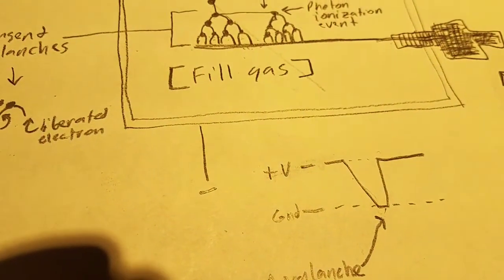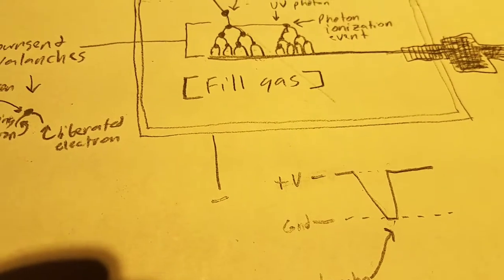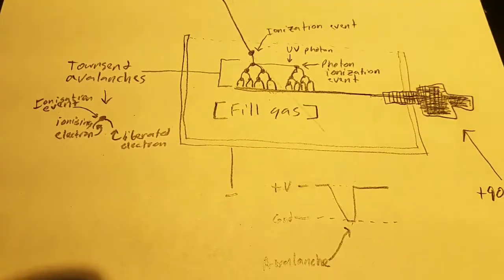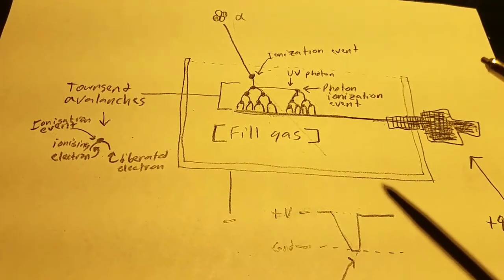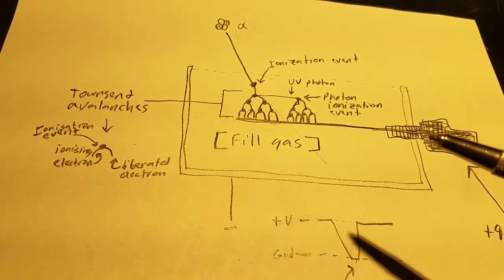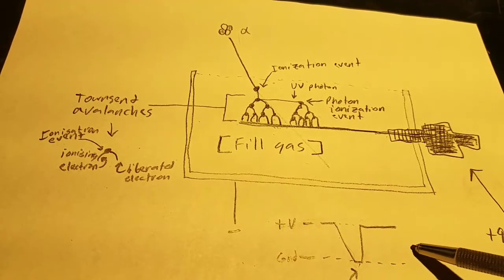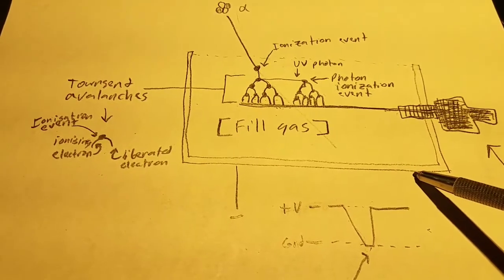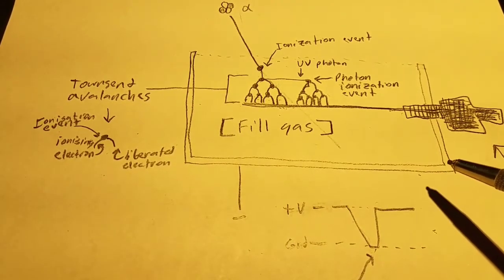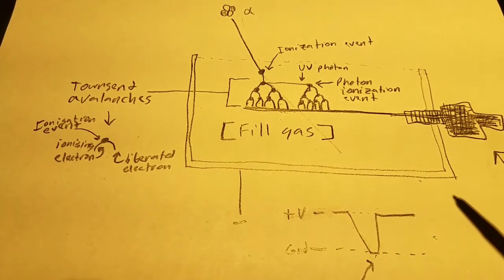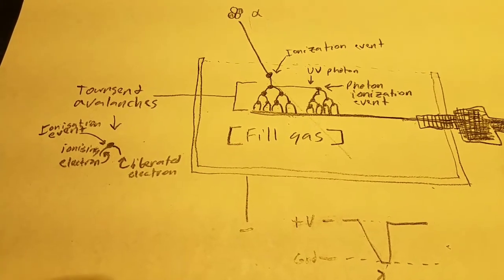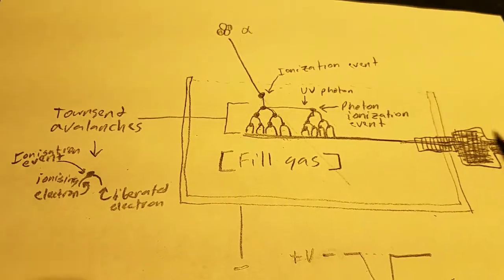That's what you actually count to figure out how many radioactive particles have collided at a certain point. You can also correlate that with radiation dose rates and later on exposure if you know what isotope you're measuring. For the particular Canberra tube that I have, it is either 3,000 or 3,300 counts per minute per microroentgen. That's the way that you can equate those.